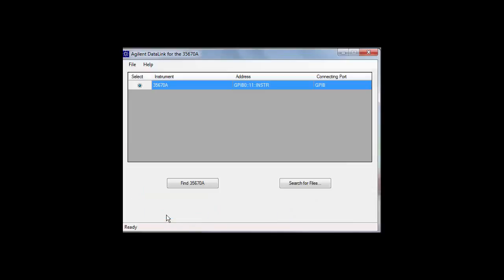If you would like to both read the files on the PC and transfer them back to the 35670A at a later time, we recommend you save the file as both .txt for reading on the PC and .sdf for loading back into the 35670A at a later time.